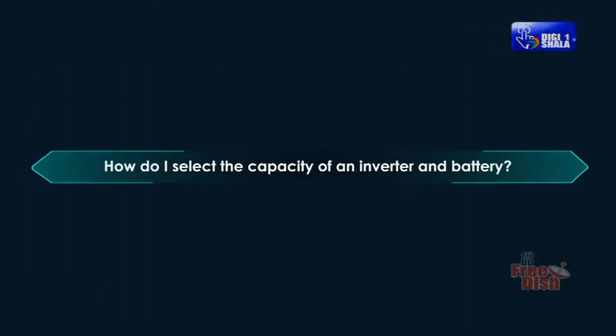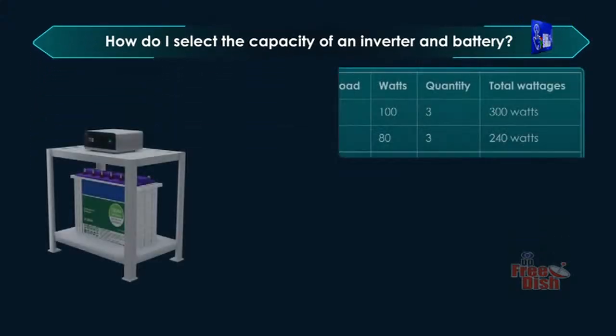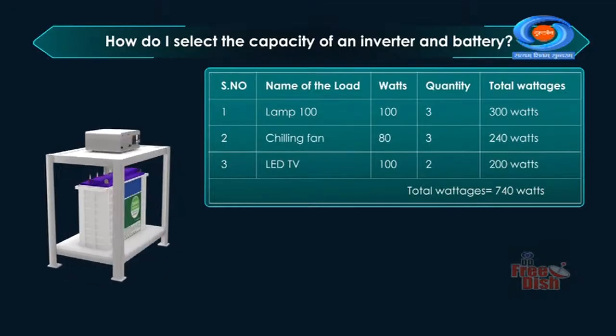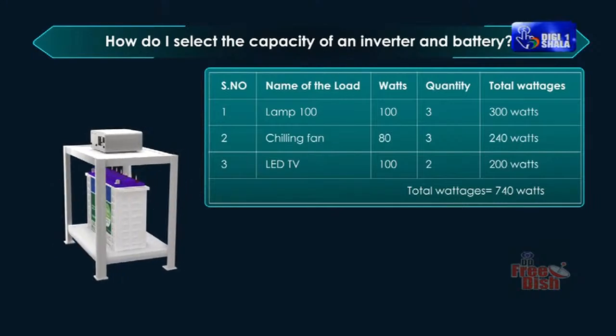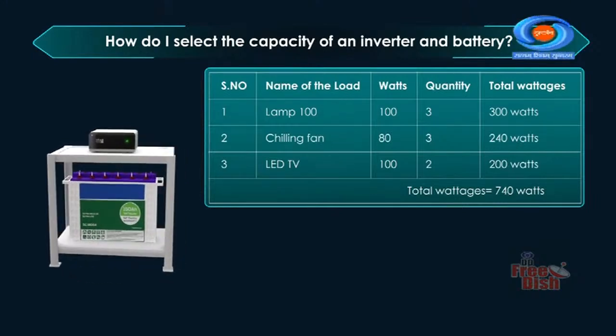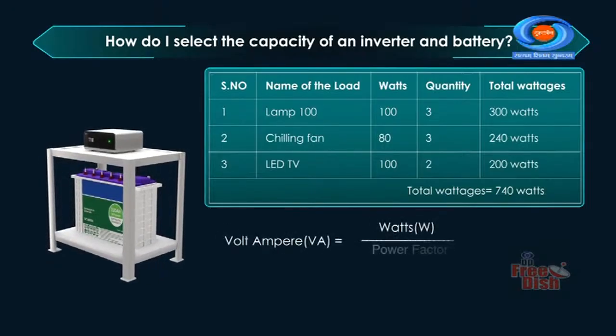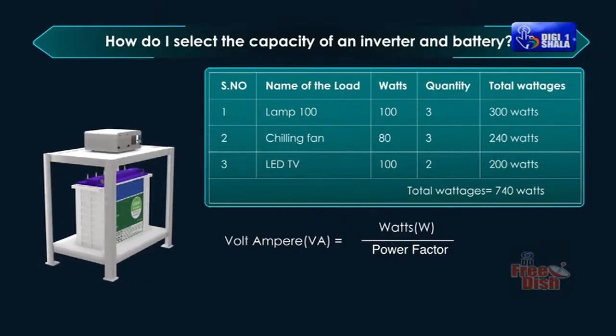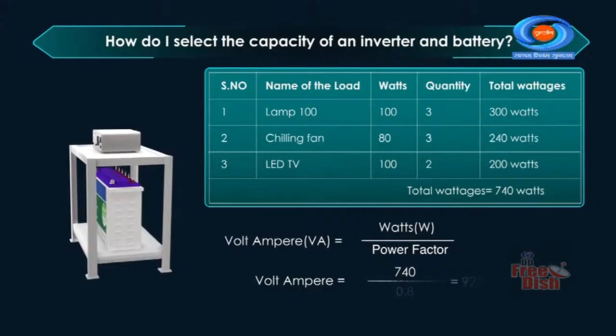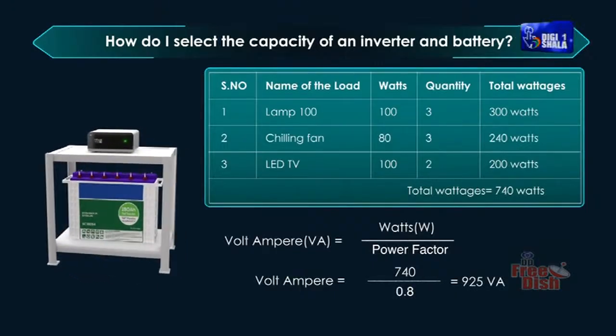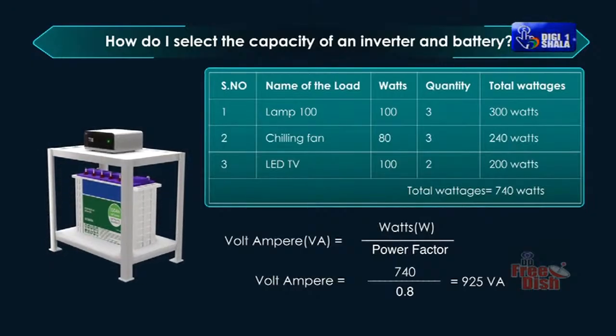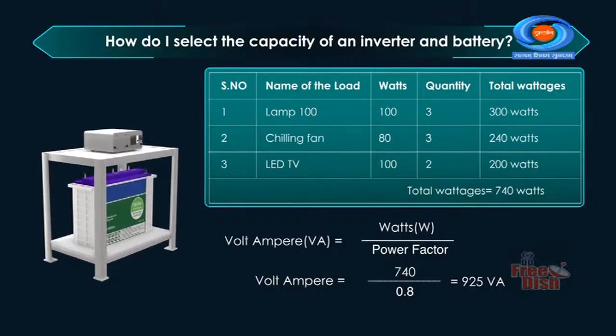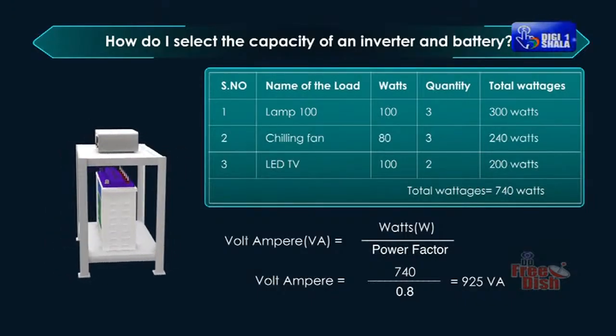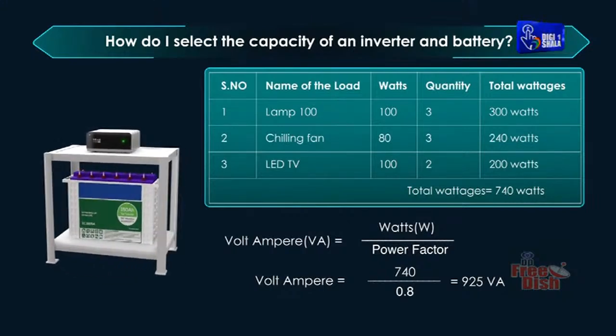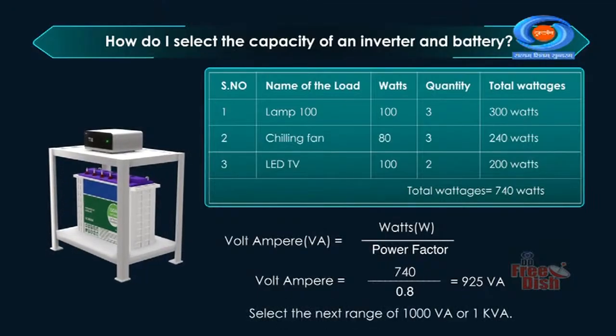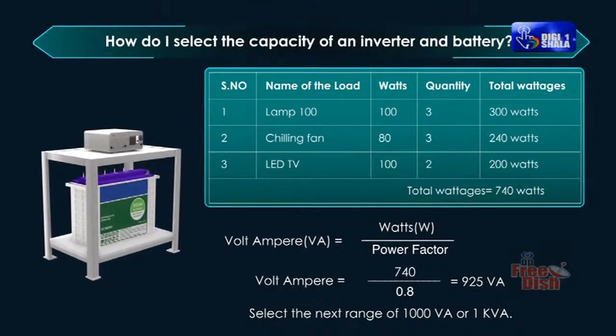How do I select the capacity of an inverter and battery? Let us assume we must design an inverter for the loads given below. From the tabulation, the total power that the inverter must supply as AC power is 740 watts. To calculate the inverter capacity in volt amperes, we must consider the power factor. Substitute the values of watts and power factor as 740 and 0.8 respectively. Since for inverters the power factor of 0.8 is standard. So, the power required for the inverter in volt amperes for the given load is 925 volt amperes. Select the next range of 1000 volt amperes or 1 kilovolt ampere.